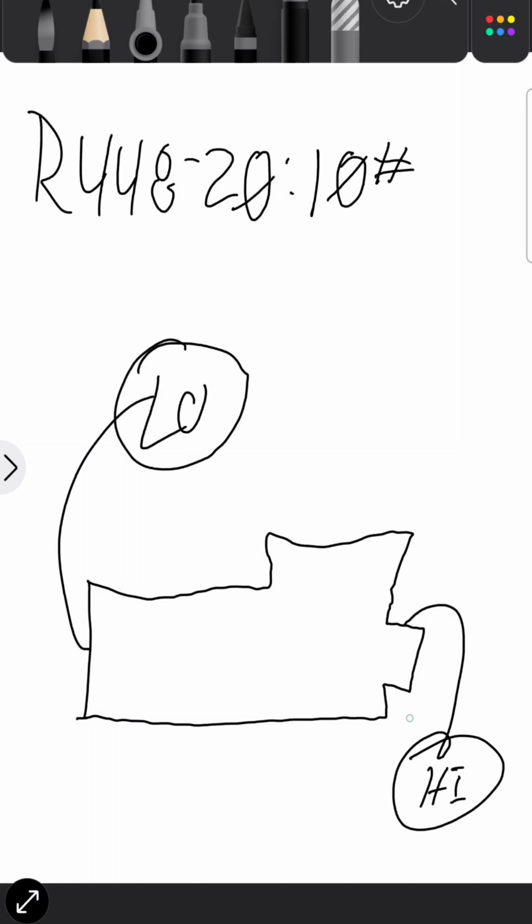The second most common thing I would say is, in these compressors, there's a pickup screen right down in here in the bottom left of the compressor, right? You'll see there's a plate right here in the bottom left of that compressor, and behind that plate, there's that screen. So what happens is you have your oil, right?